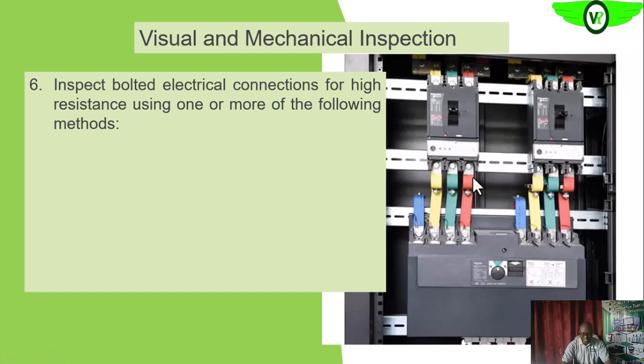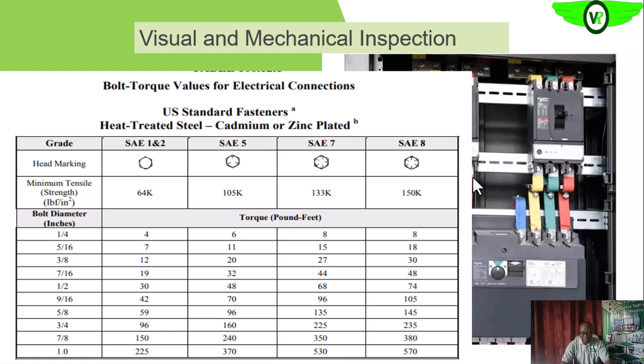So still on the mechanical or visual inspection, we also want to look at these bolted electrical connections. We want to look at the torque to see that the actual torque level is applied. Okay, so if we do not have one specified for our facility, or the manufacturer does not specify any for this cabinet, you can check the table and use this table to apply the normal torque value. The different bolt grades have different torque values.